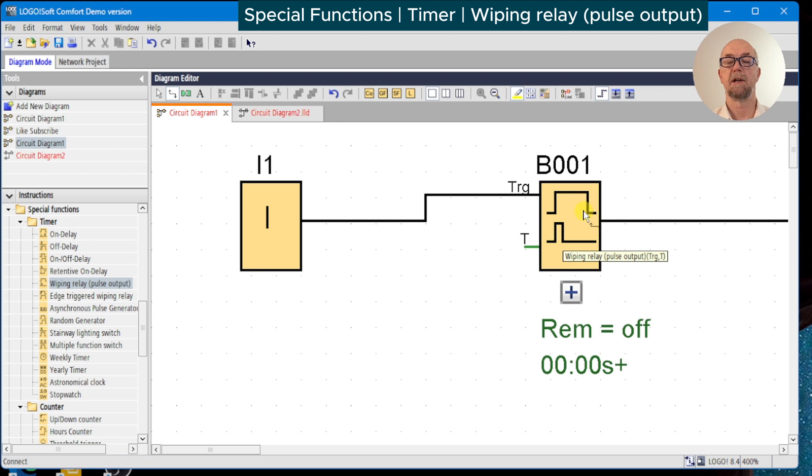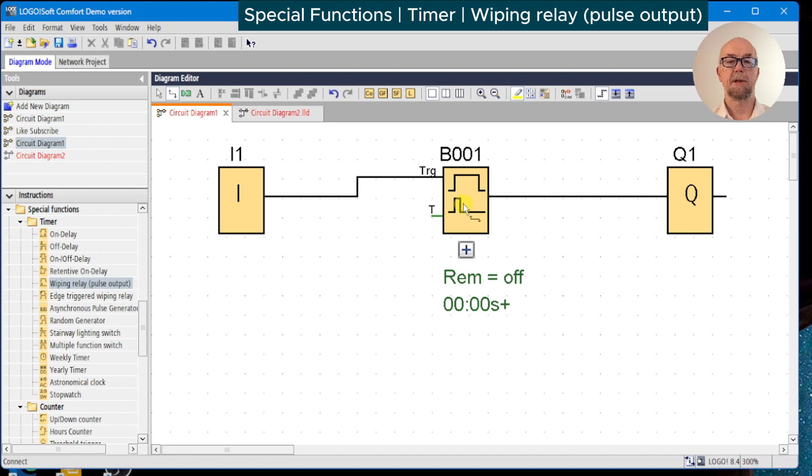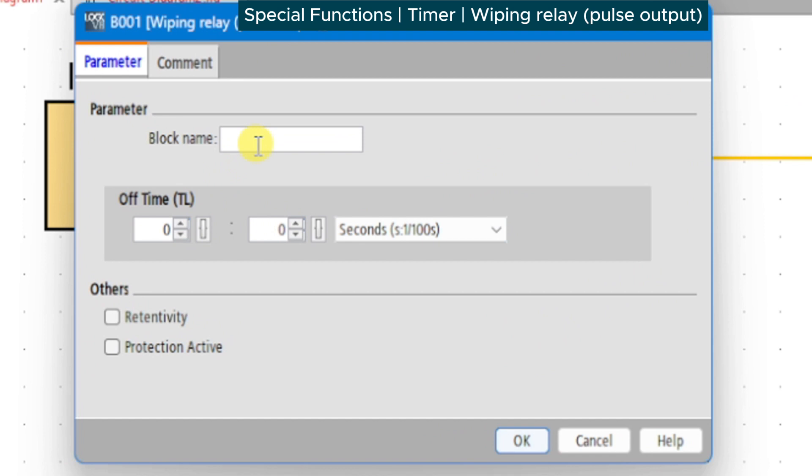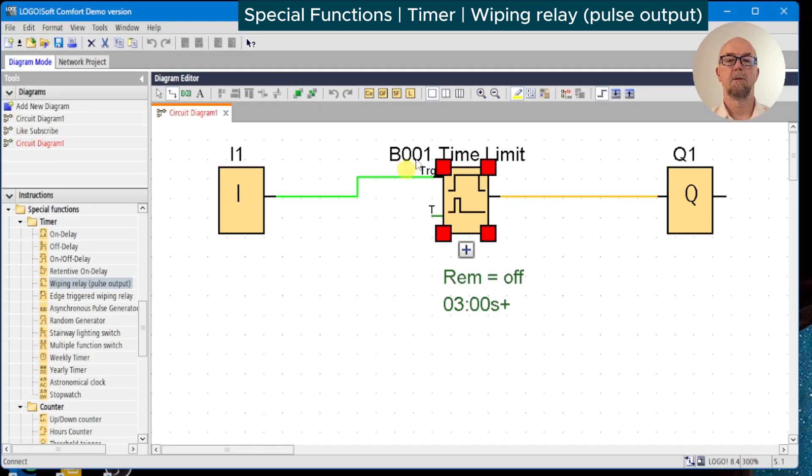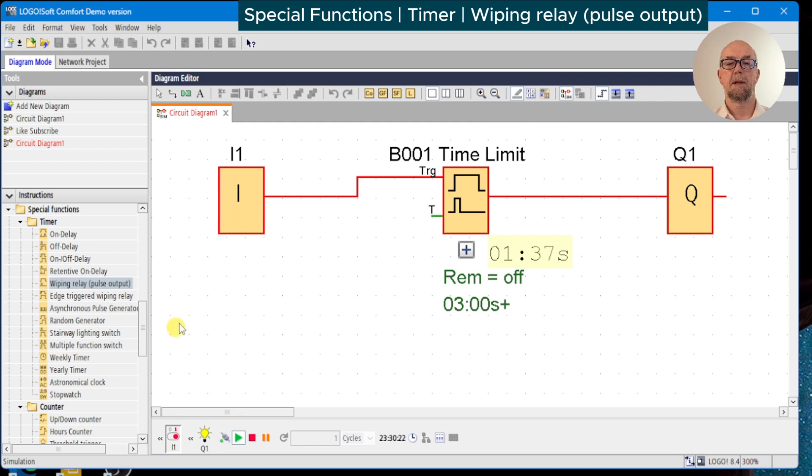There's some details we'll cover as we go along. We will set some parameters on this and document as always, so we're going to call this time limit and we will set it for a three second delay. We'll switch the simulator on, switch on the input, output turns on immediately, and at three seconds the output turns off again.